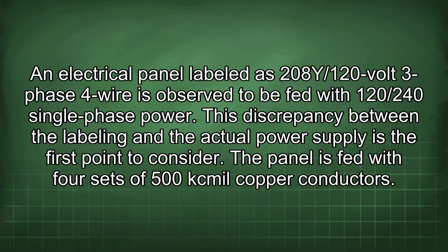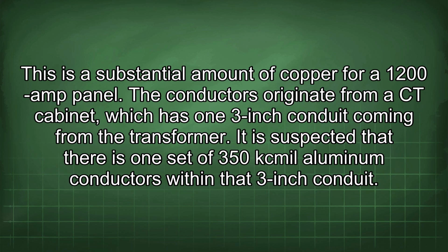An electrical panel labeled as 208Y/120V 3-phase 4-wire is observed to be fed with 120/240 single-phase power. This discrepancy between the labeling and the actual power supply is the first point to consider. The panel is fed with 4 sets of 500 kcmil copper conductors. This is a substantial amount of copper for a 1200 amp panel.